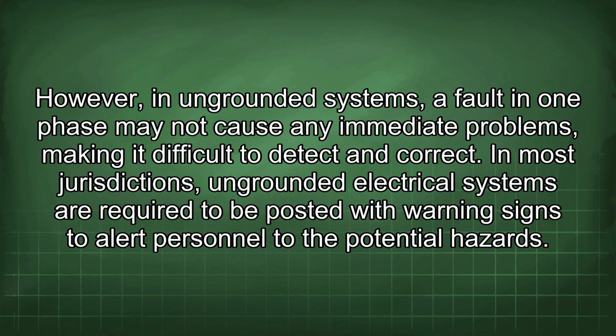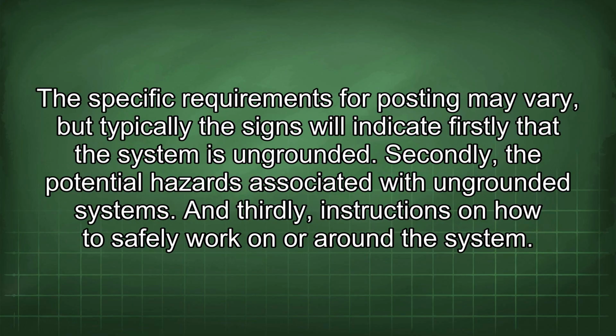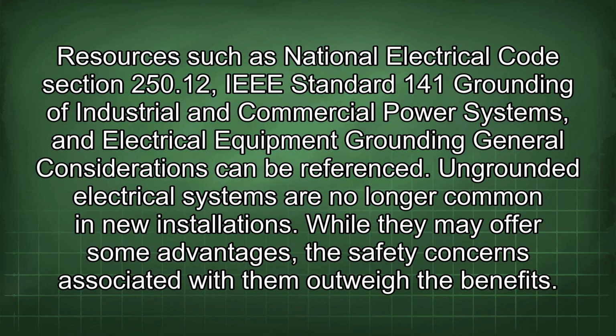In most jurisdictions, ungrounded electrical systems are required to be posted with warning signs to alert personnel to the potential hazards. The specific requirements for posting may vary, but typically the signs will indicate firstly that the system is ungrounded. Secondly, the potential hazards associated with ungrounded systems. And thirdly, instructions on how to safely work on or around the system. Resources such as National Electrical Code Section 250.12, IEEE Standard 141, grounding of industrial and commercial power systems, and electrical equipment grounding general considerations can be referenced.